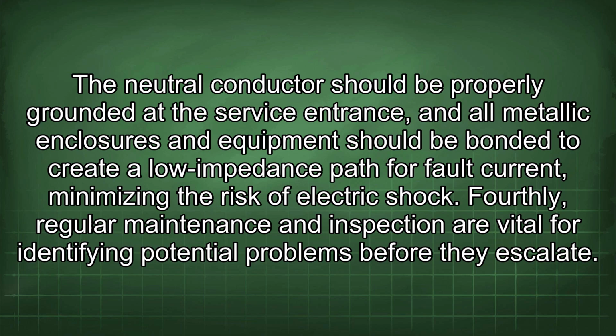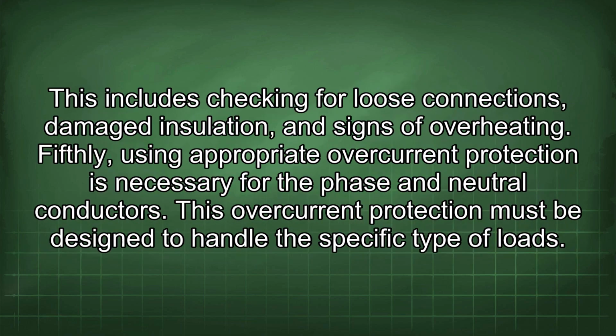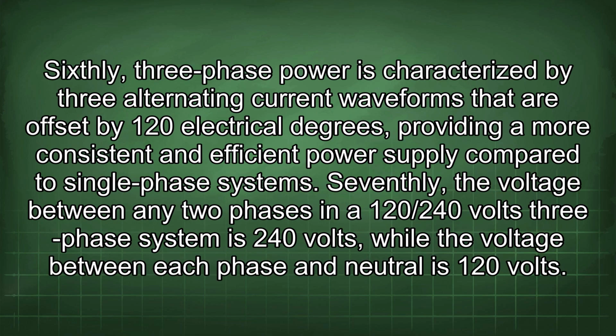Fourthly, regular maintenance and inspection are vital for identifying potential problems before they escalate. This includes checking for loose connections, damaged insulation, and signs of overheating. Fifthly, using appropriate overcurrent protection is necessary for the phase and neutral conductors. This overcurrent protection must be designed to handle the specific type of loads. Sixthly, three-phase power is characterized by three alternating current waveforms that are offset by 120 electrical degrees, providing a more consistent and efficient power supply compared to single-phase systems.